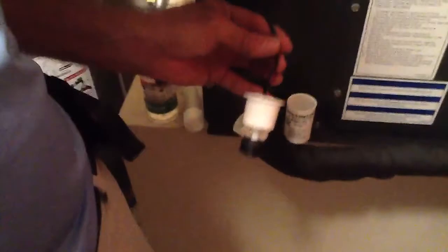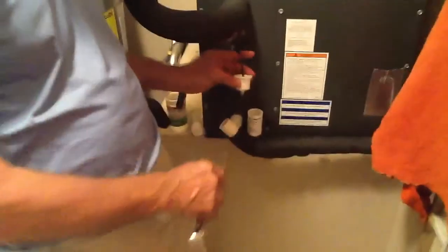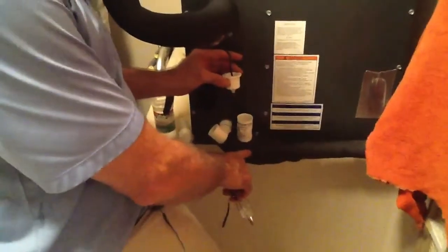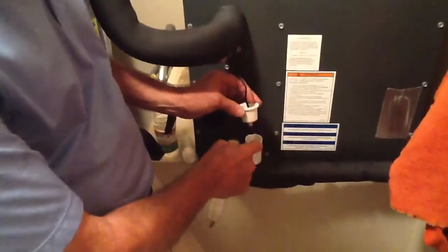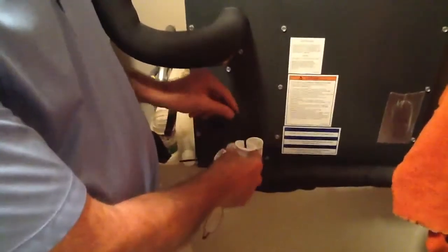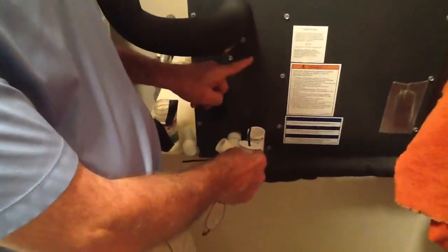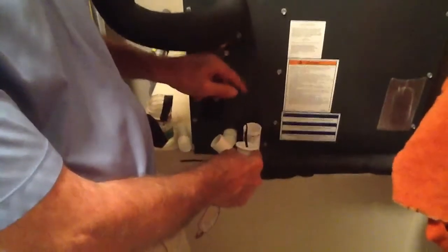What I want to talk about today is the SS2 switch. The purpose of this switch is when the water backs up in the main condensate line that goes to the outside, the water will back up in the pan, come out right here about halfway down, and this switch — as it goes up — will shut the unit down. This thing is wired through the thermostat and the red wire coming off the air handler, so basically it breaks the red. That's how this works.